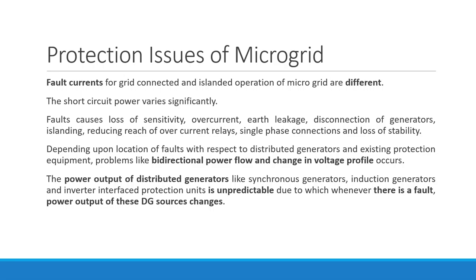The power output of distributed generators, which may consist of synchronous generators, induction generators, and inverter interface protection units, will be unpredictable. Whenever there is a fault, the power output of these sources changes. There is a fault, so the power output is going to change. So that is basically unpredictable.